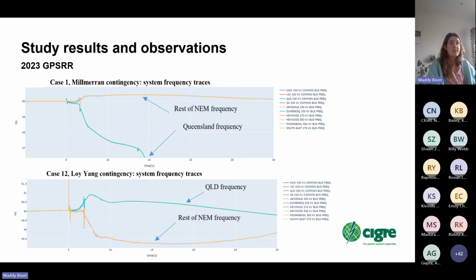Then in terms of the graphs that are shown here, firstly, the graph at the bottom shows the loss of the Loy Yang B and Valley power units. So again, we looked at several different cases and we saw that the QNI distance protection operated to trip QNI for high Queensland export cases in response to the remote generation contingency.